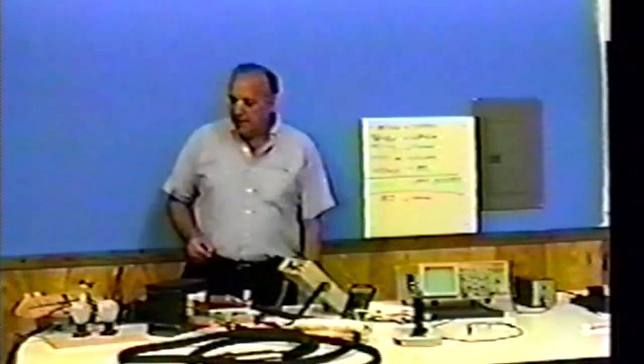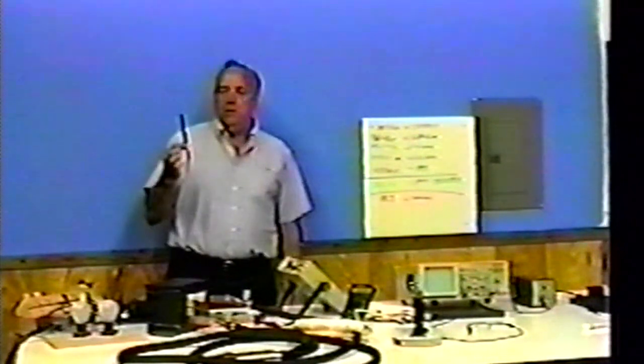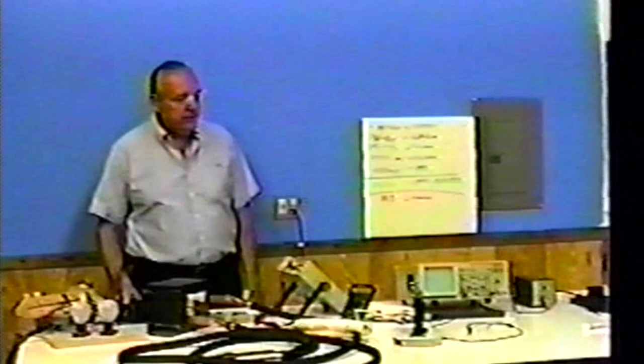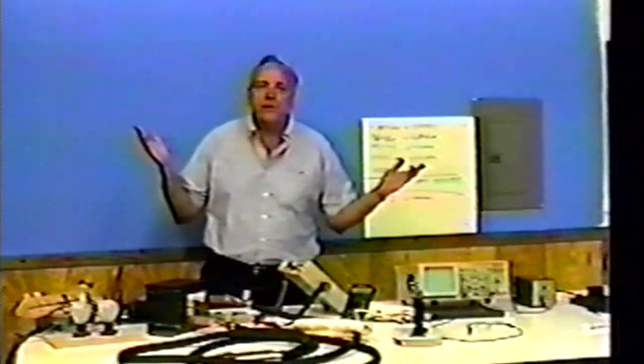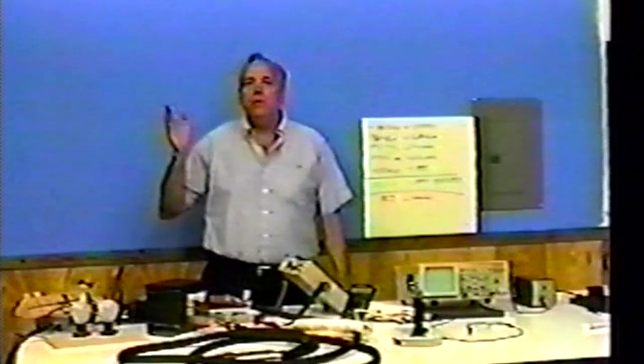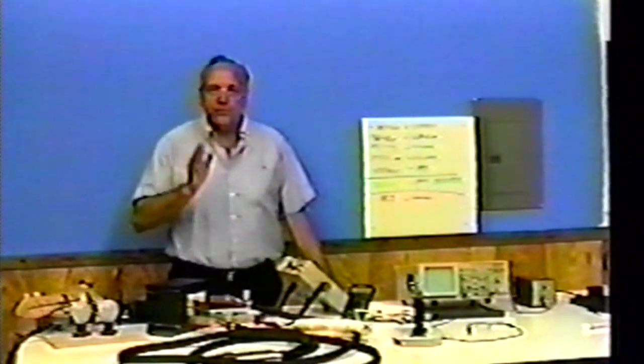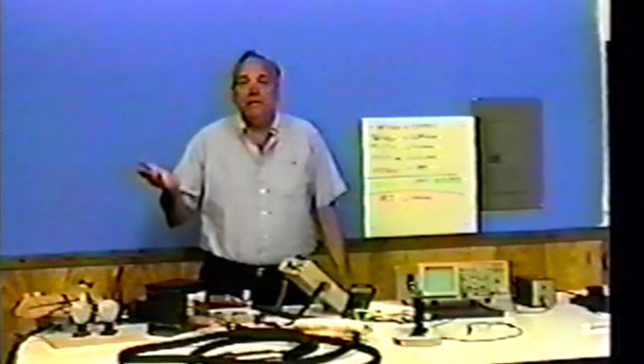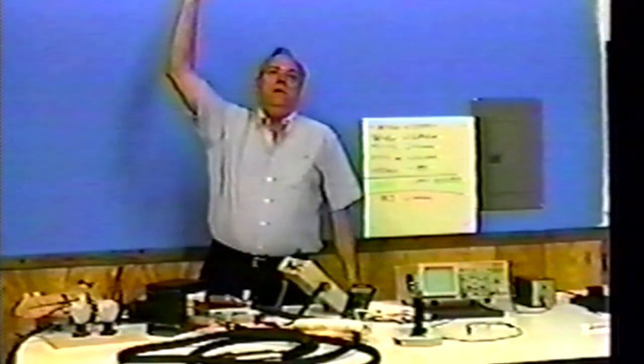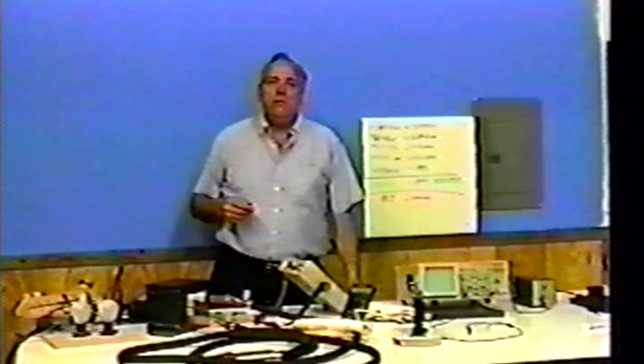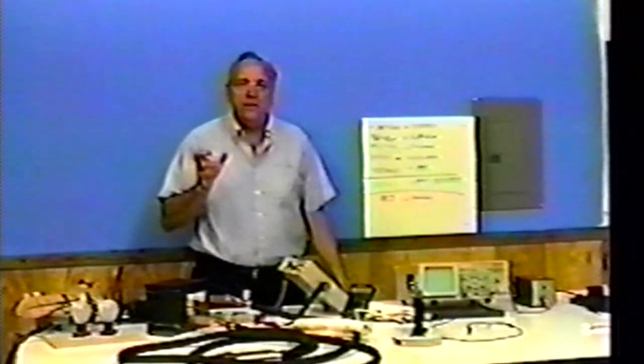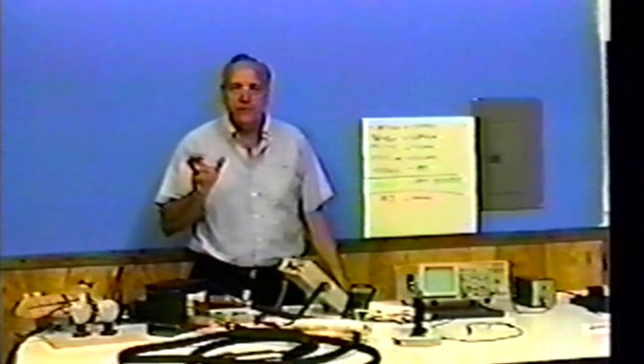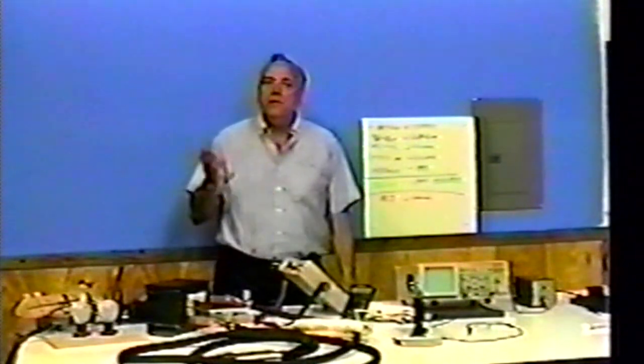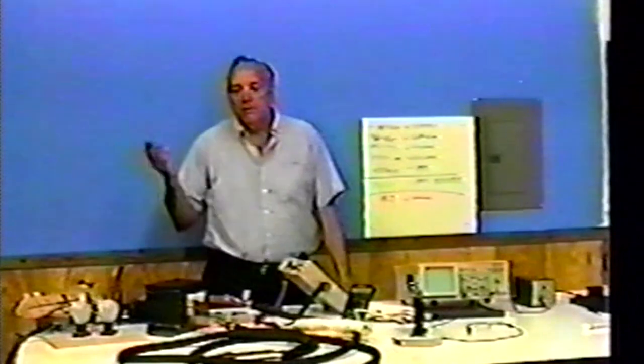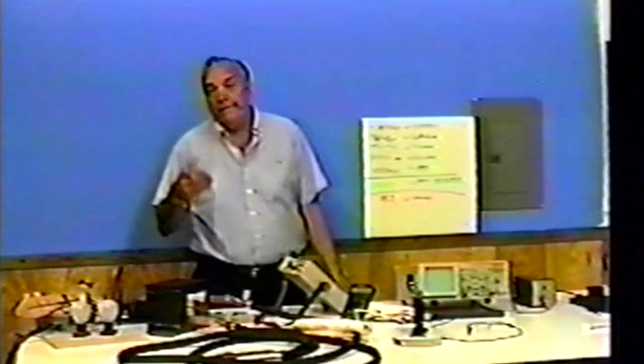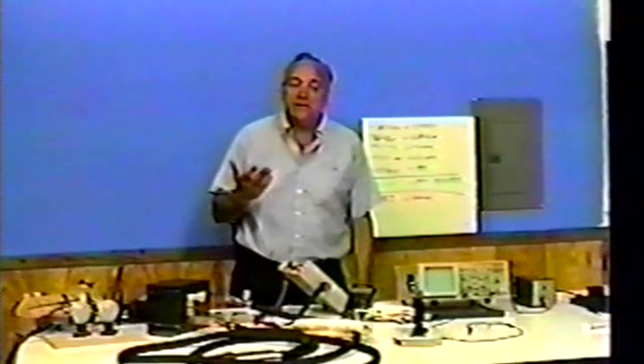What they're talking about is narrower than that probe. I don't have anything on the table that's as narrow as 1400 hertz. So it just is not true. It's not that it's untrue that they've got a peak current of something, but it's a useless piece of information. What we need to measure is true RMS over 15 cycles. If they're not doing that, they're just making up stories. The number they have is kind of interesting, curious information, but it's not something useful.